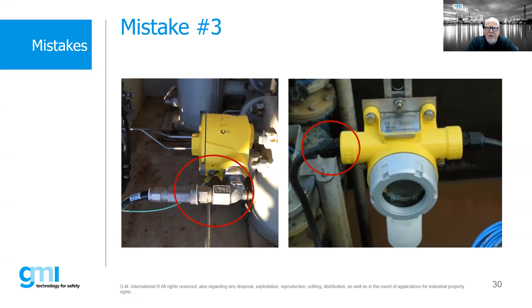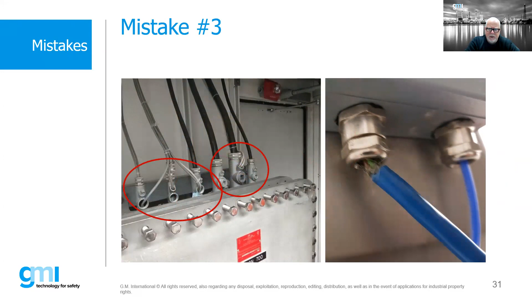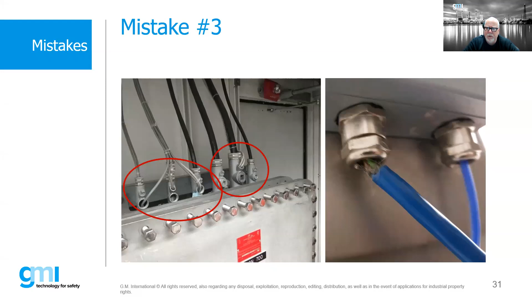These are pictures of some other installations. In the United States, people often use seal fittings, known internationally as stopper boxes. We spend a lot of money on an expensive, large explosion-proof or flame-proof box with nice bolts, but then don't seal them properly, defeating the whole purpose of having that enclosure. On the right-hand side, we see an installation with cable glands that are not properly sealed.